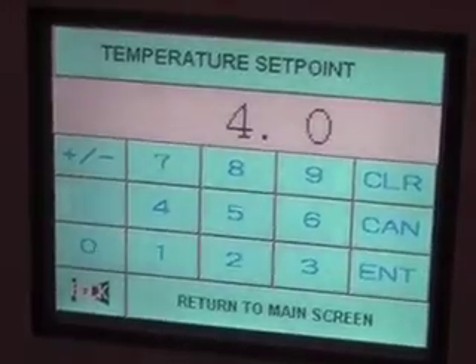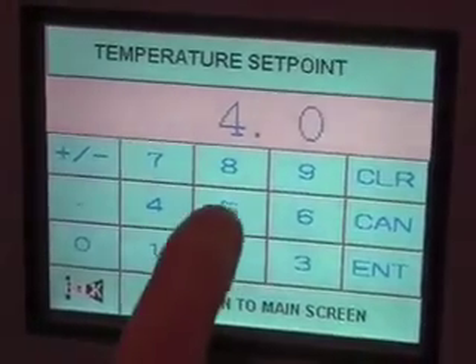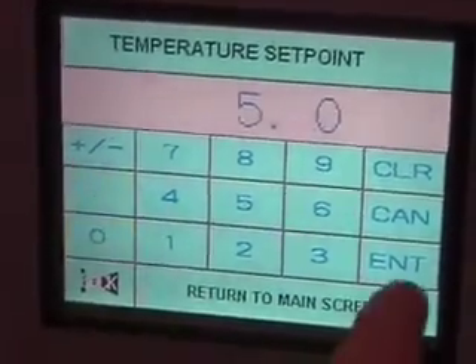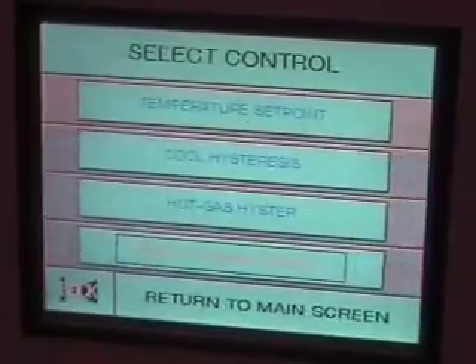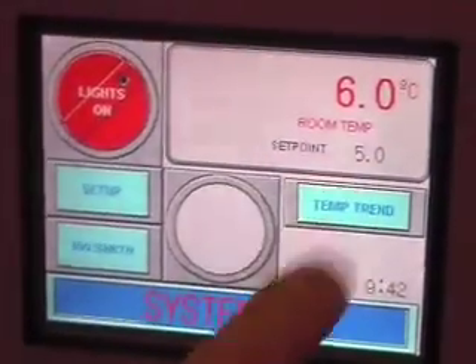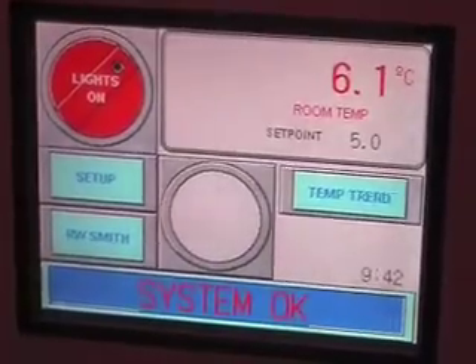Okay. Control setup. You have your temperature set point. We talked about 4 degrees. If you wanted, say, 5 degrees, if I said I want 5.0, and you hit enter. Turn to the main screen. See, now it wants to maintain 5 degrees.